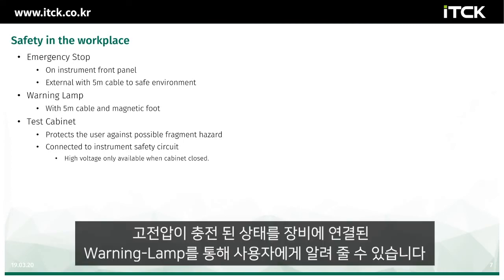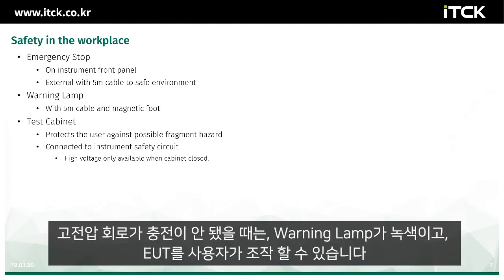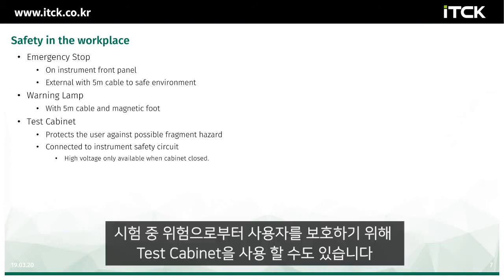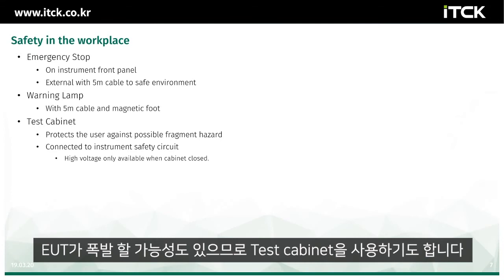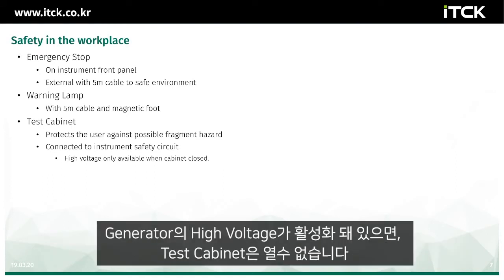A warning lamp connected to the instrument indicates when the high voltage circuits are active. When the high voltage circuits are deactivated, the warning lamp is green and the test object can be manipulated. A test cabinet is provided to protect the user against a possible fragmentation hazard should an EUT explode unexpectedly. The test cabinet is connected to the instrument safety circuit so that when the high voltage is enabled, the test cabinet cannot be opened.